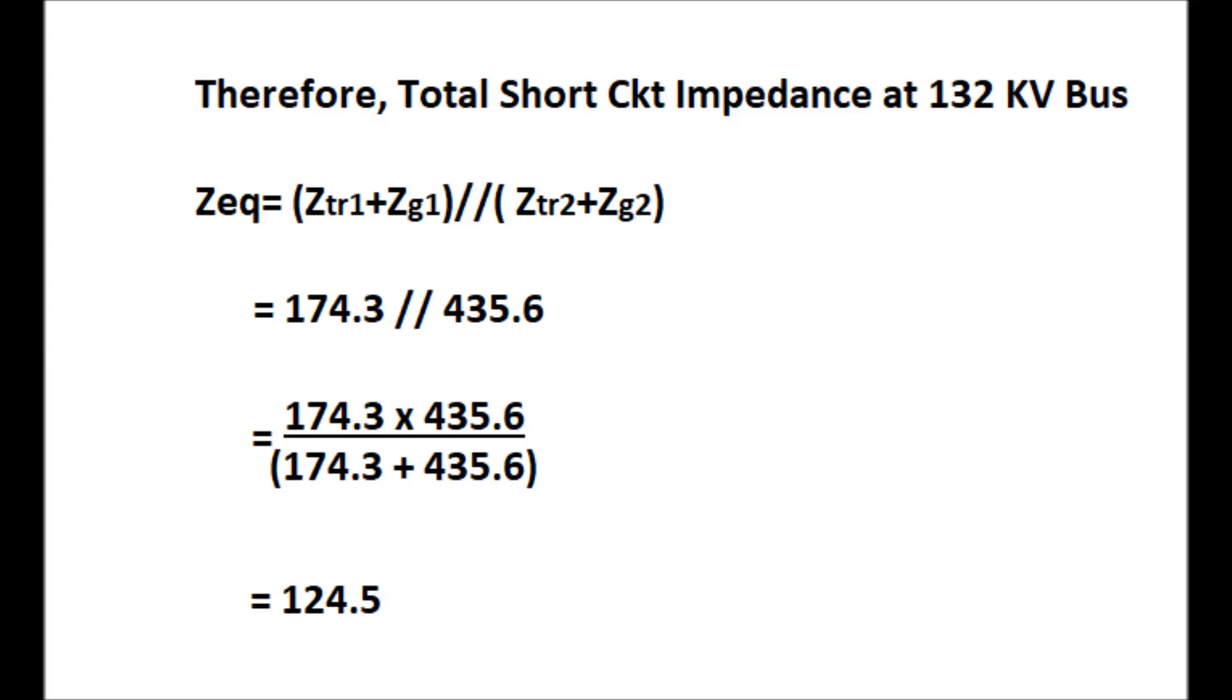Therefore, the total short circuit impedance at 132 kV bus will be Z equivalent equal to ZTR1 plus ZG1 in parallel with ZTR2 plus ZG2. This parallel equivalent impedance will come to 124.5 ohm.